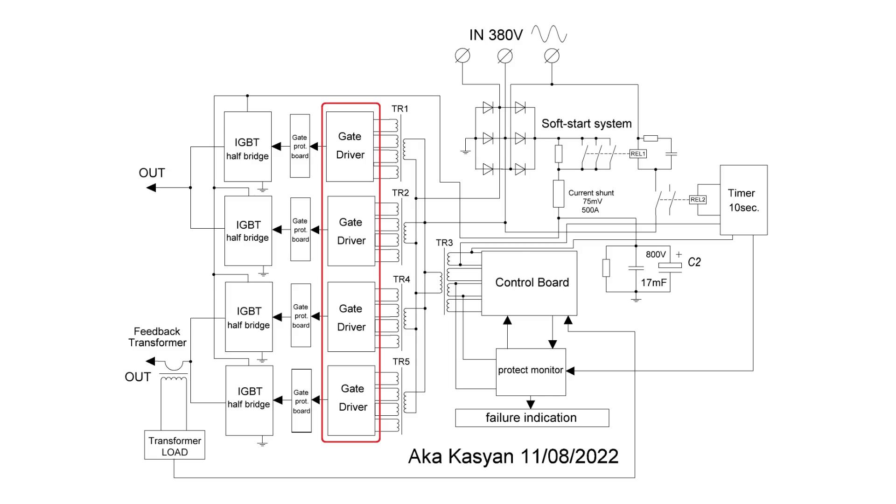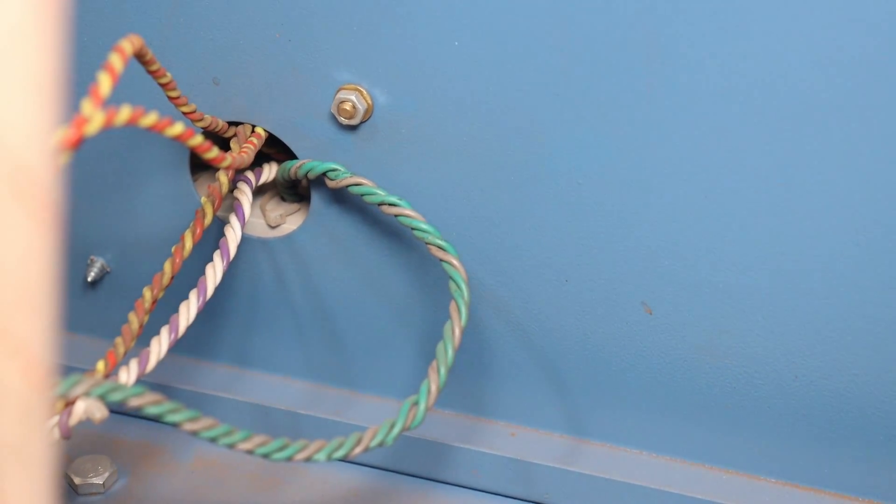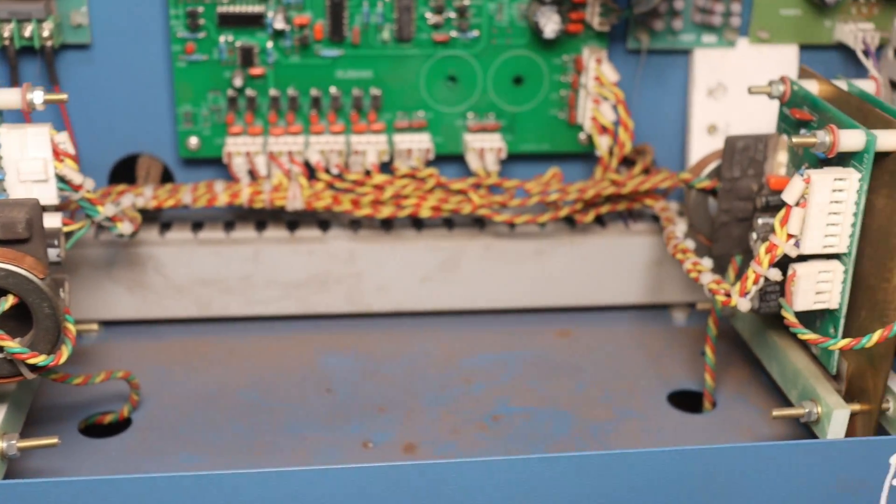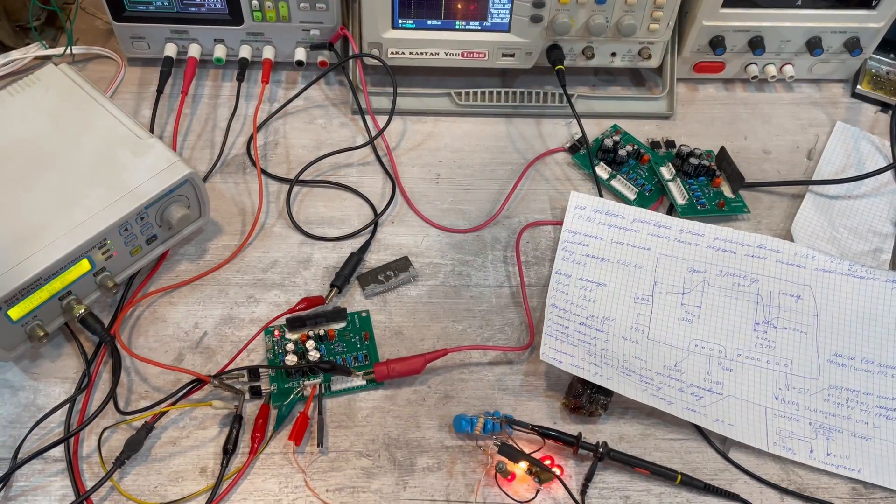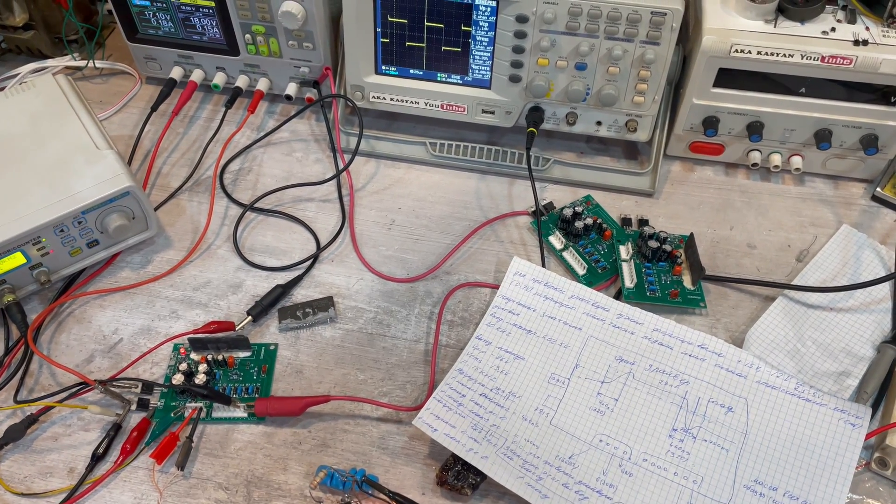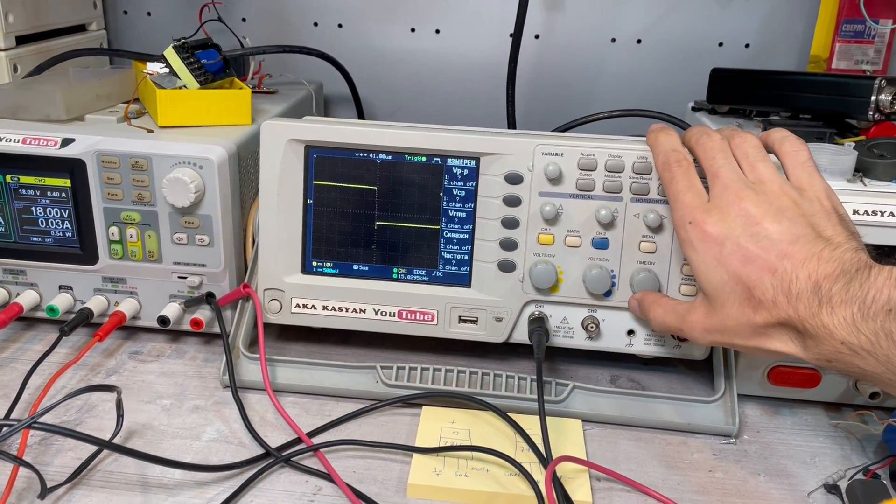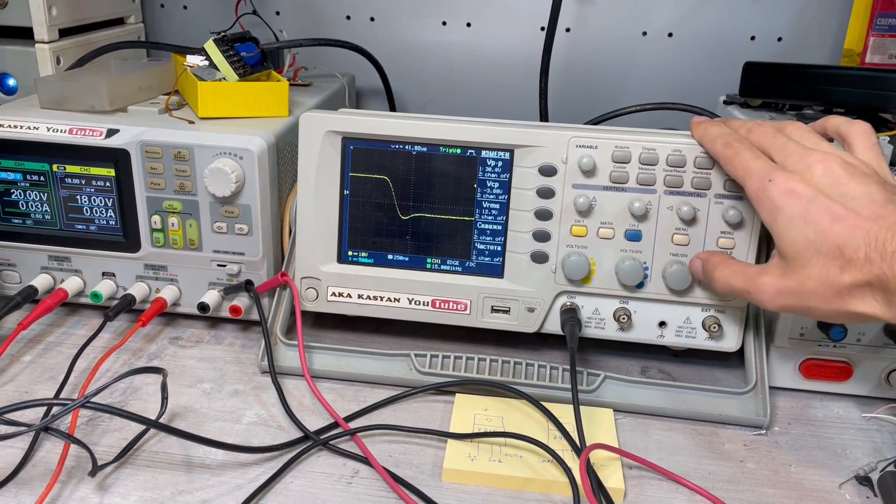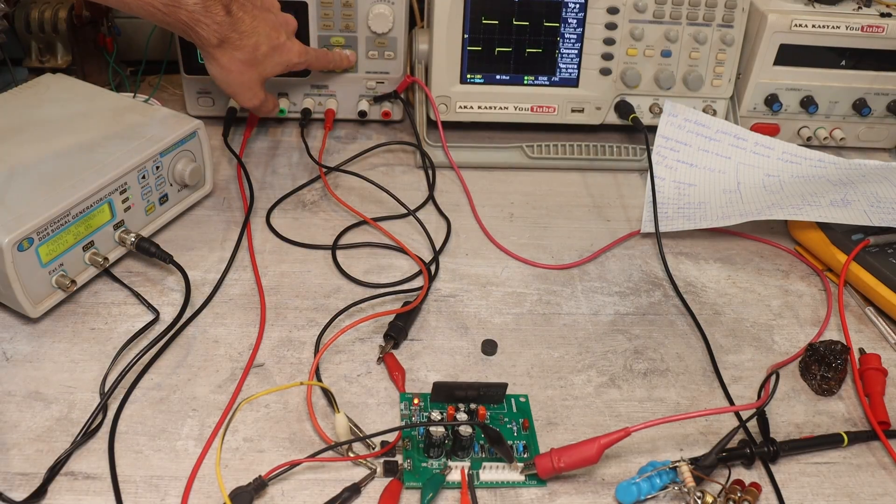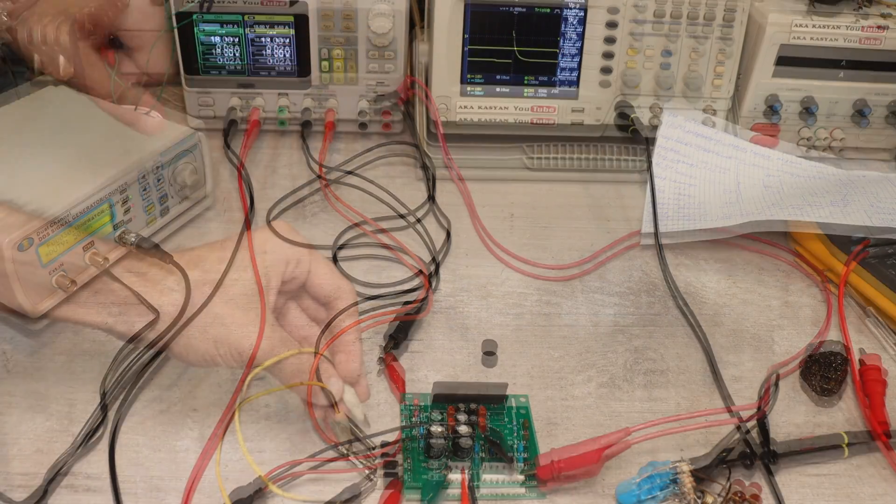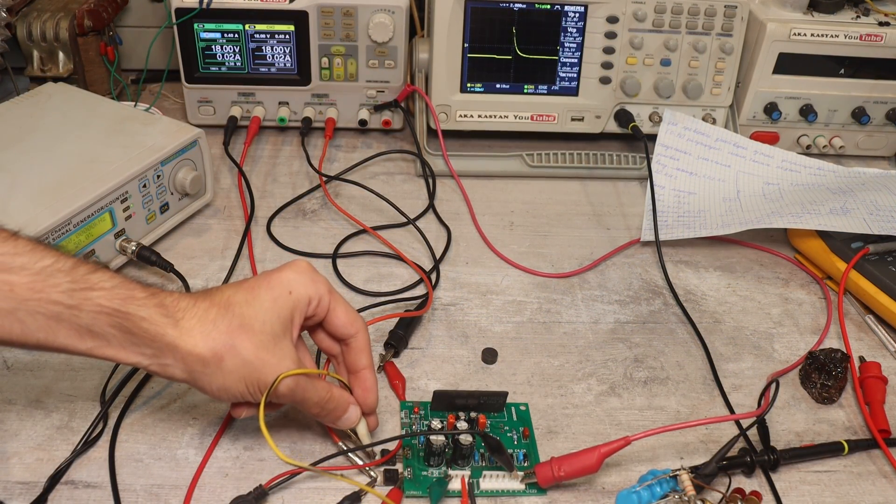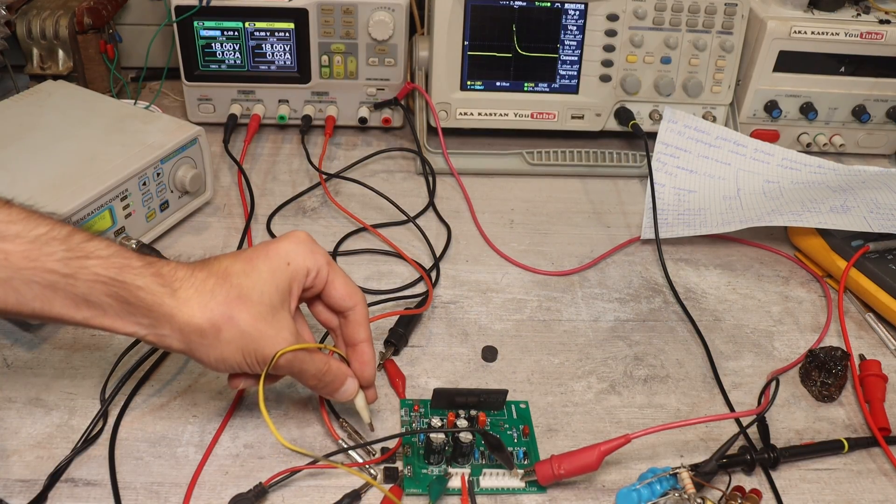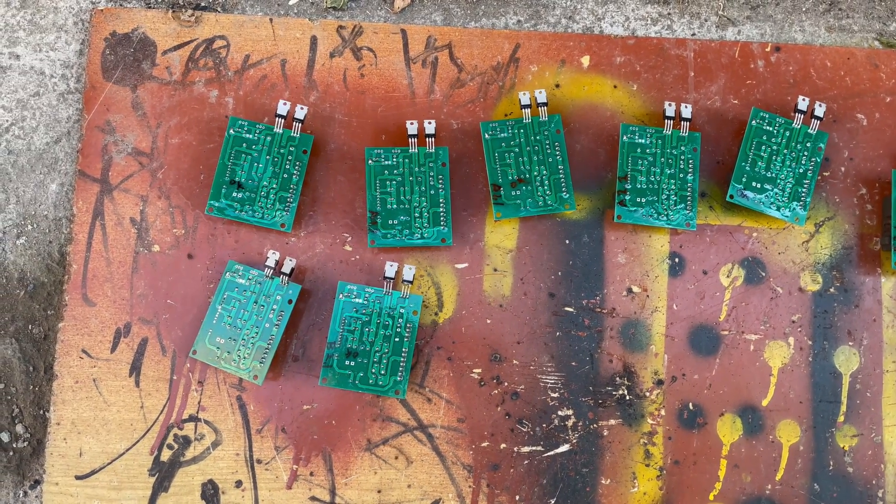Drivers are perhaps the most time-consuming node for diagnostics, because there are 8 drivers here and each needs to be checked in different modes under different loads and currents and with simulated gate capacitance. Next, oscillograms are taken with the measurement time of rise and fall and pulse amplitude. Then the correct operation of the driver is checked, for example if the control signal or feedback disappears. In case of any accidents, the driver must output negative signal at the output thereby reliably closing the transistor switches. If by chance they appear high level, the switches will fail. All 8 drivers were checked and then all obtained values were compared.